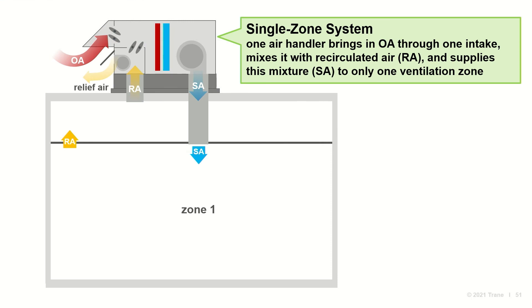In a single zone system, one air handler serves the ventilation needs of one zone. All the outdoor air that enters through the intake is delivered to that single zone, and any recirculated air is merely return air from that same zone. Examples include package rooftop units, classroom unit ventilators, and small single zone air handling units.